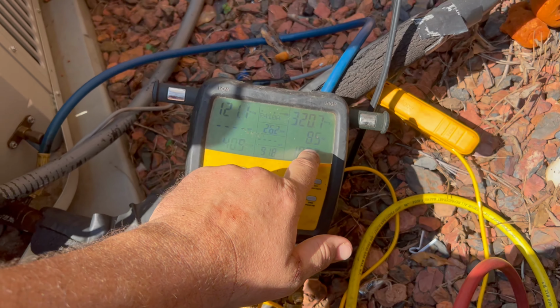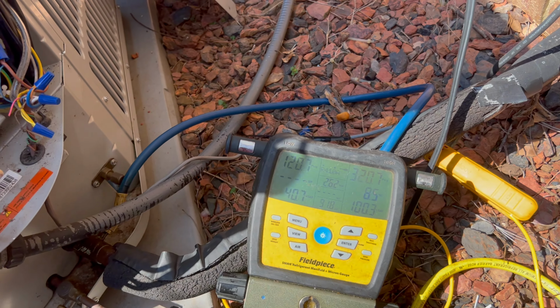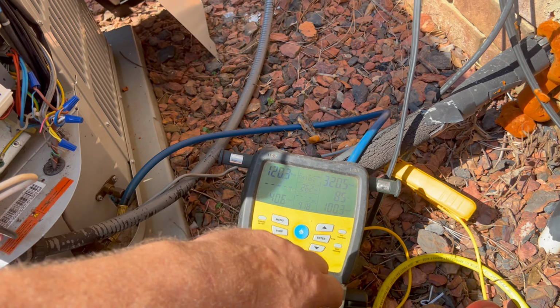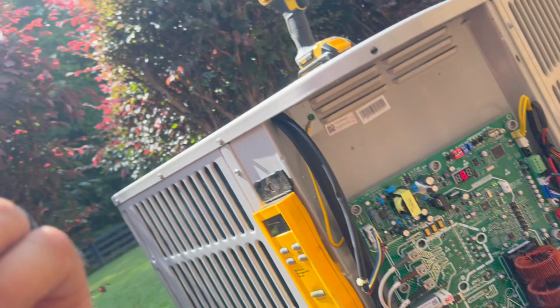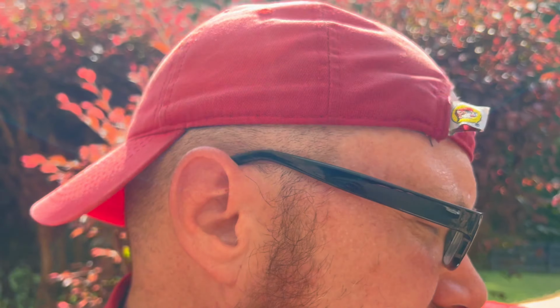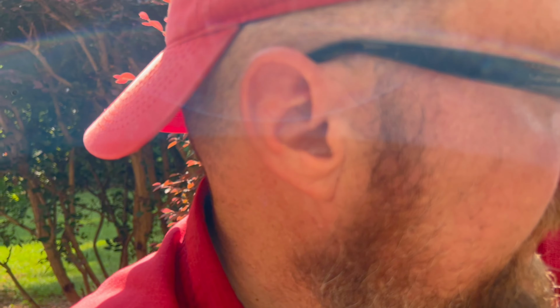Alright, we're at 8.5 subcooling, 40 degree vapor saturation point, 100 degree liquid saturation point. This particular unit calls for about 10 degrees subcooling, plus or minus 3. So we're within that margin of error. We are running in basically forced high speed mode for charging, but we'll leave it this way for this particular cycle because they are about 90 degrees inside right now. So we'll just let it complete this cycle in high speed mode essentially.